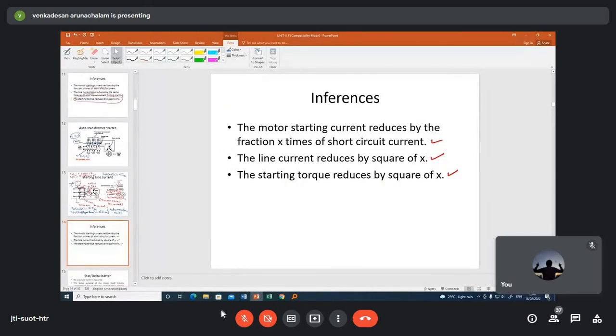So you see, these are the inferences. The motor starting current reduces by a fraction X of the short circuit current. The line current reduces by the square of X. And of course, the starting torque is reduced by the square of X, so you cannot avoid that. Any doubt here? If you have any doubt, you can ask me.